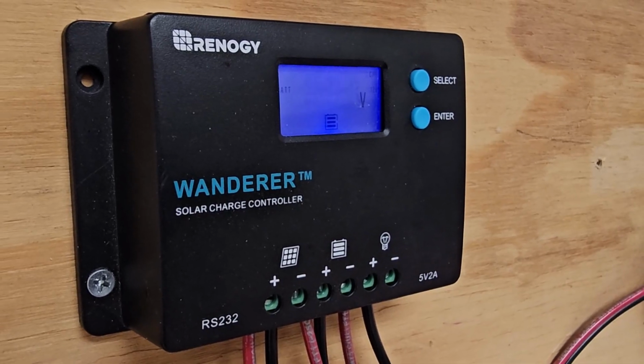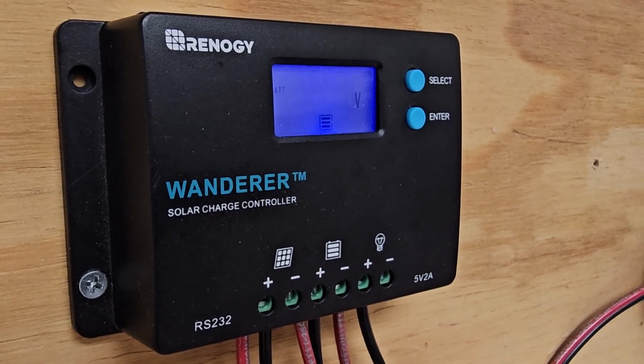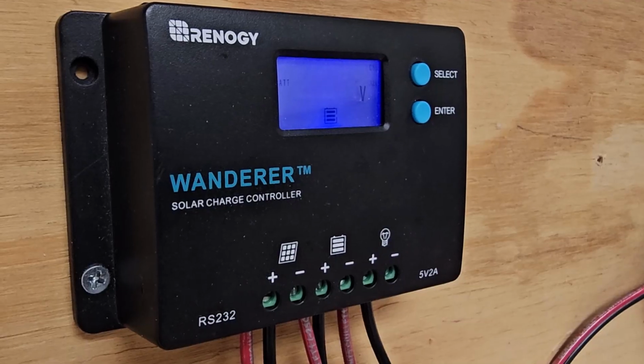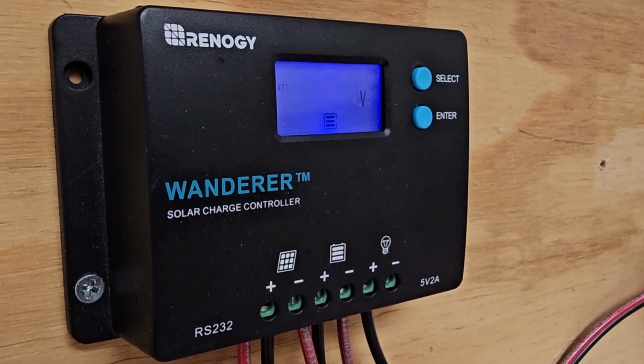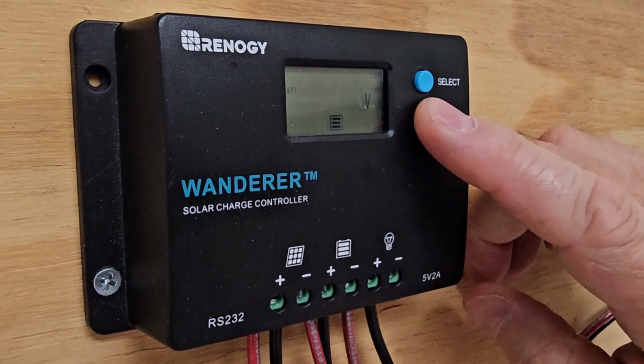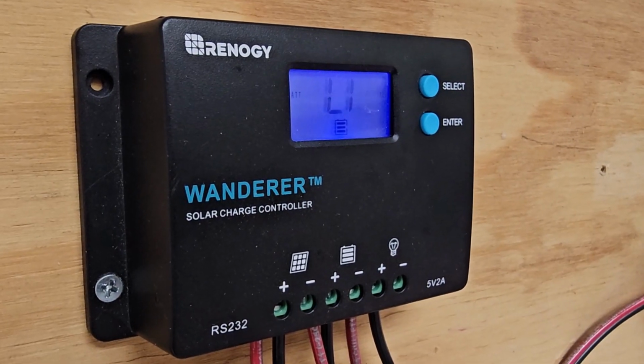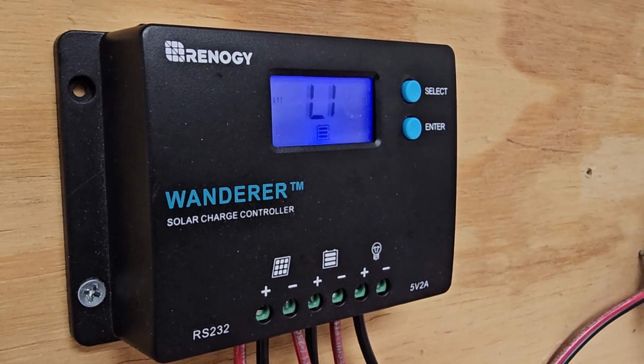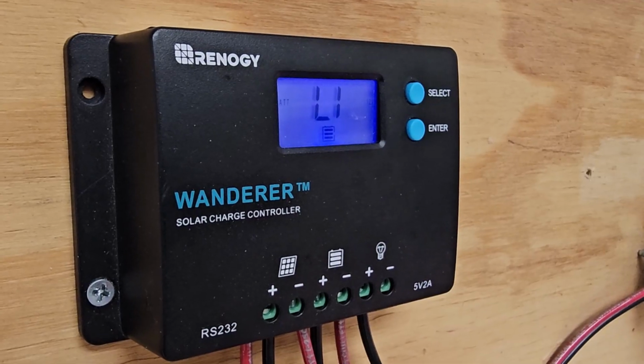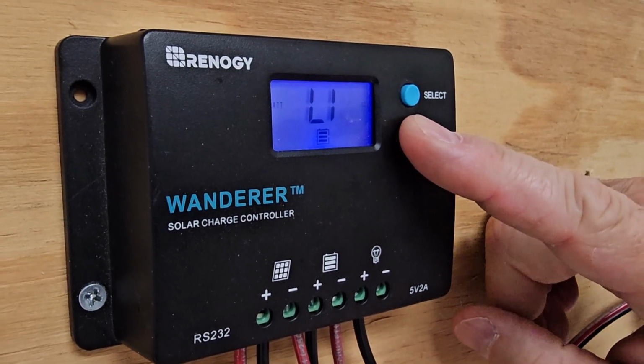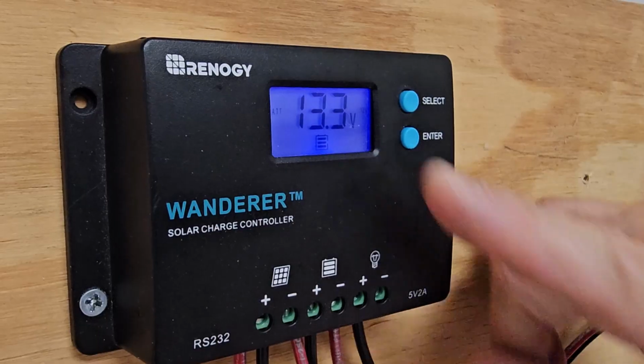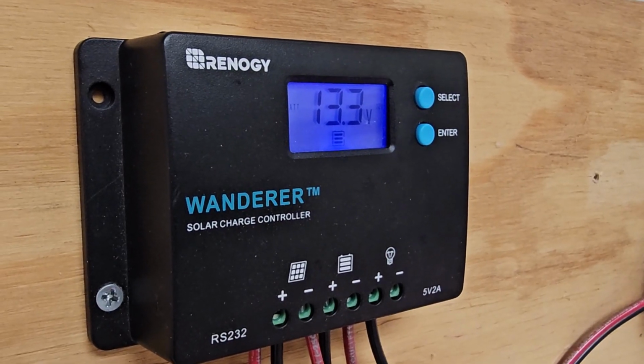Next, the charge controller screen shows 14.2, the setting for the maximum battery voltage the charge controller will permit. Press Enter to accept 14.2. Li will reappear on the screen. Press Enter for 3 seconds to exit the battery type programming menu.